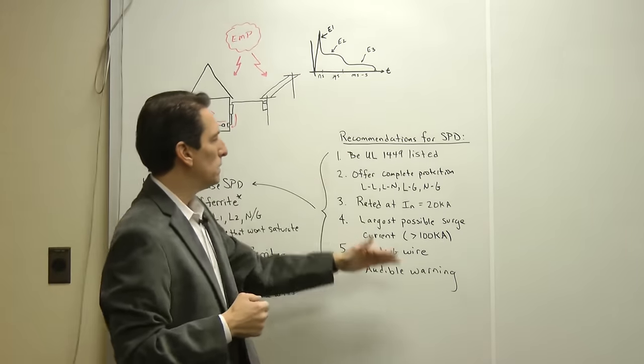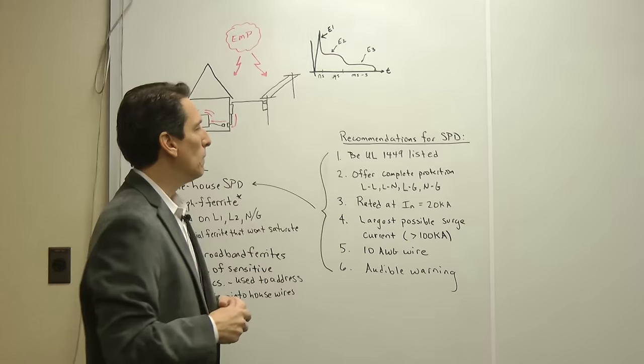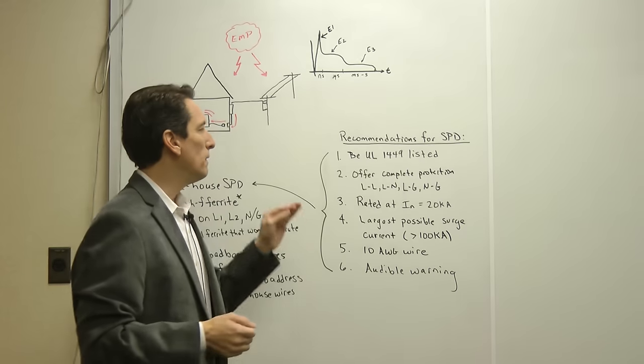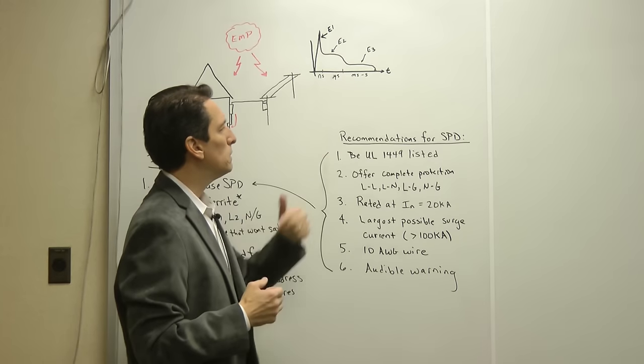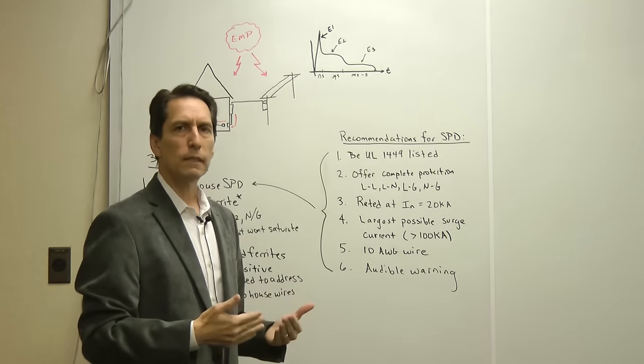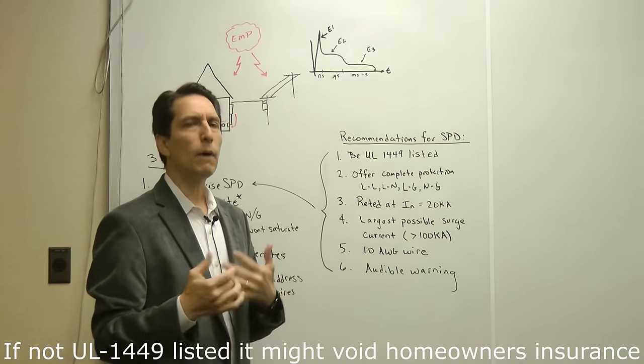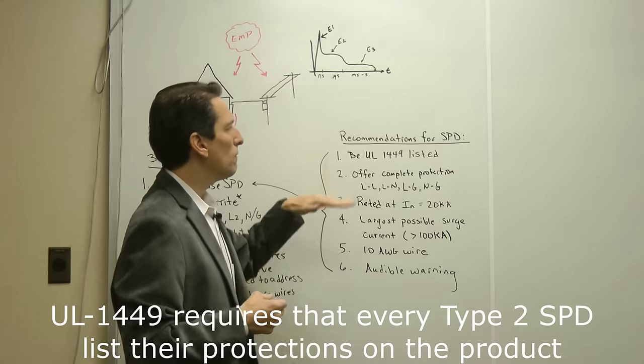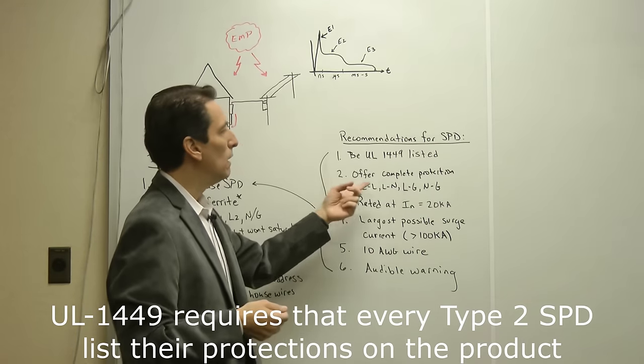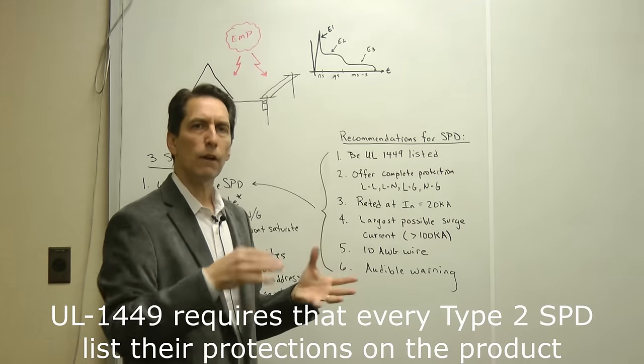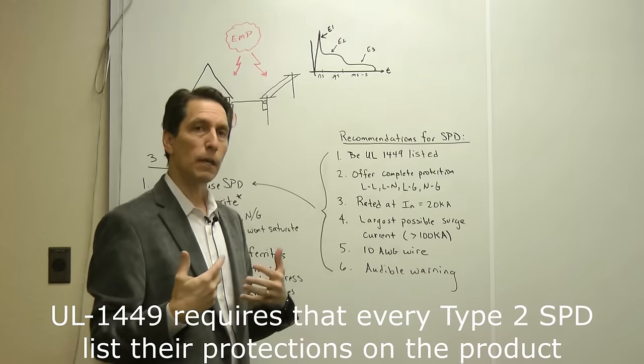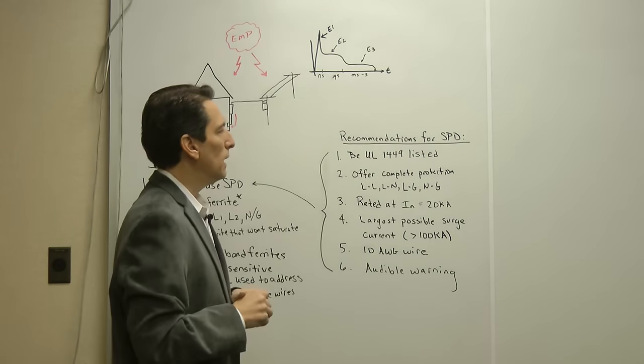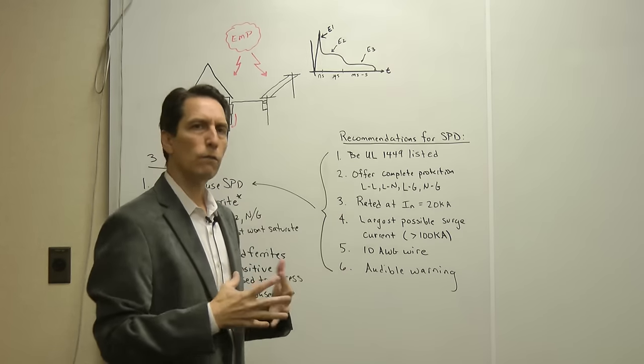I came up with six metrics that I think are important for a good whole-house surge protection device. The first is get one that's UL 1449 listed — that means it's been properly tested for safety. If you get one that's not UL 1449 listed, it might void your homeowner's warranty. Second, it has to offer complete protection for your home: line-to-line, line-to-neutral, line-to-ground, and neutral-to-ground. It has to protect all those different paths by which current could flow, because you don't know where the energy is coming in.